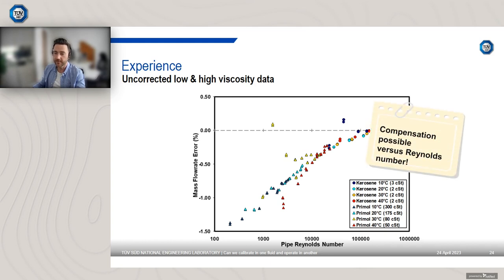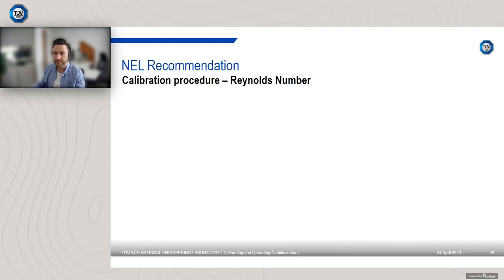So what do we recommend at NEL? We recommend that you can potentially compensate with respect to Reynolds number, but you have to perform significant characterization of your device with respect to Reynolds number. So what would that look like? Well, here's what we recommend for the calibration procedure.